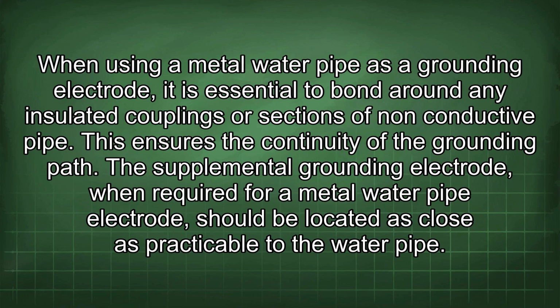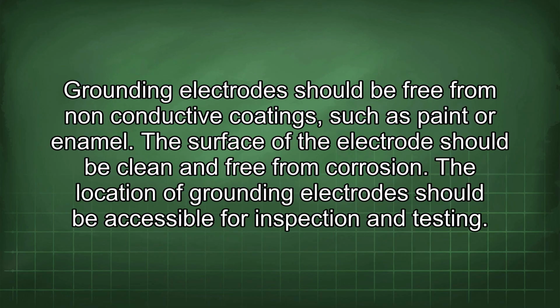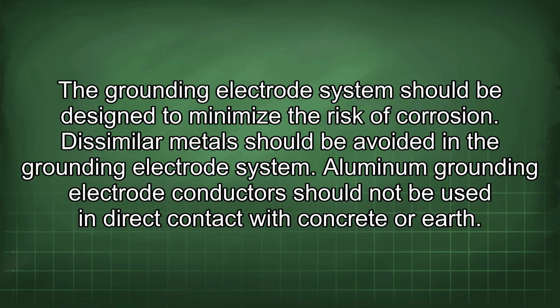The supplemental grounding electrode, when required for a metal water pipe electrode, should be located as close as practicable to the water pipe. Grounding electrodes should be free from non-conductive coatings such as paint or enamel. The surface of the electrode should be clean and free from corrosion. The location of grounding electrodes should be accessible for inspection and testing. The grounding electrode system should be designed to minimize the risk of corrosion. Dissimilar metals should be avoided in the grounding electrode system. Aluminum grounding electrode conductors should not be used in direct contact with concrete or earth.